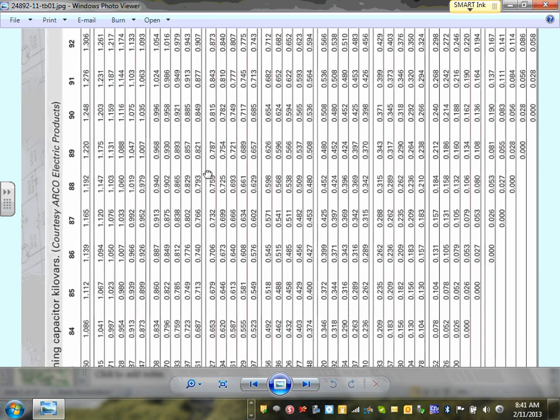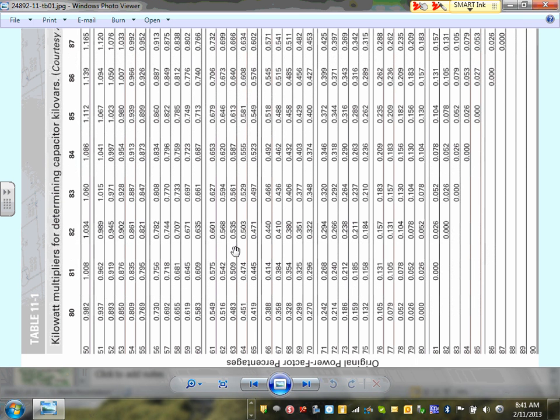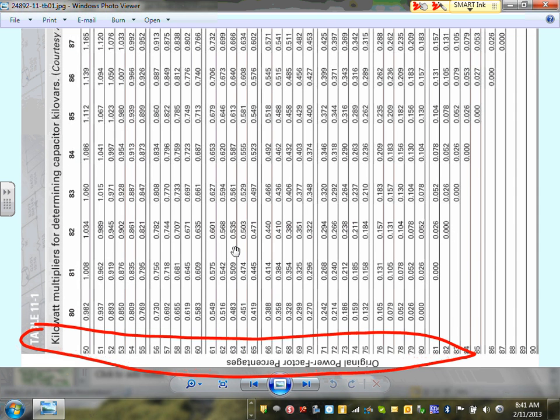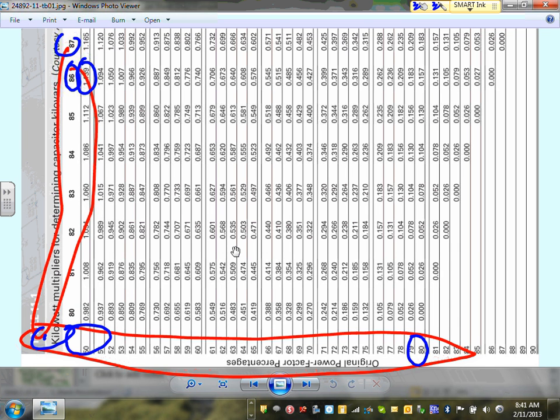All right, here we go. So anyway, if you guys look at the bottom here, these are your original power factor right here. And these are the corrected power factor that you want to correct to. So if I want to correct, look at this nasty power factor. My existing power factor is 50, and I need to correct to an 86. I can't read this one. So that's the multiplier that you need when you size your capacitors. If my power factor is 80, and I need to correct to 87, that's not a good correction. My multiplier will be this value. So I'll show you guys how to use this one tomorrow when we're doing the calculation.